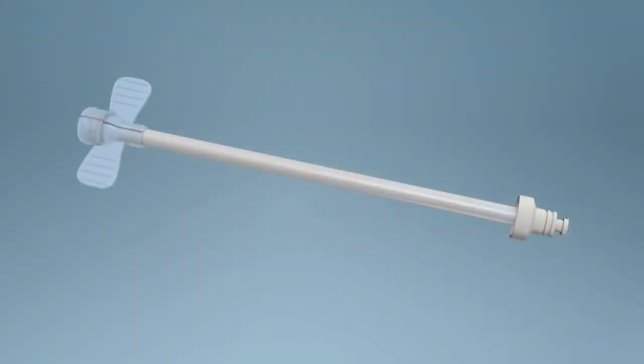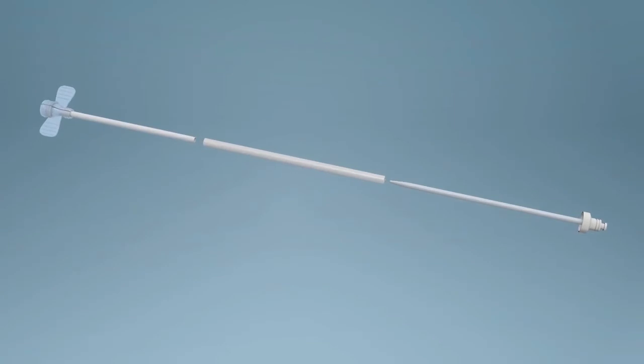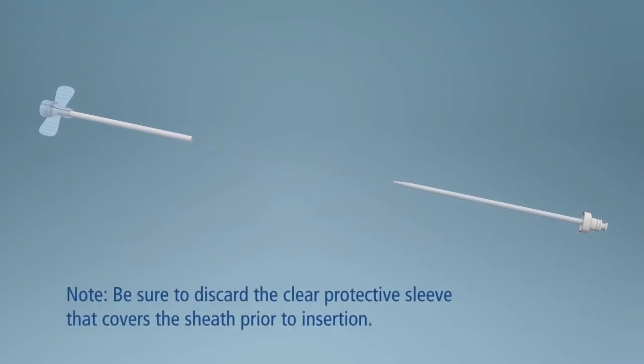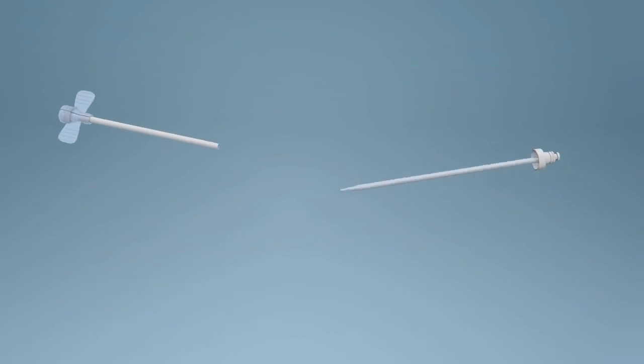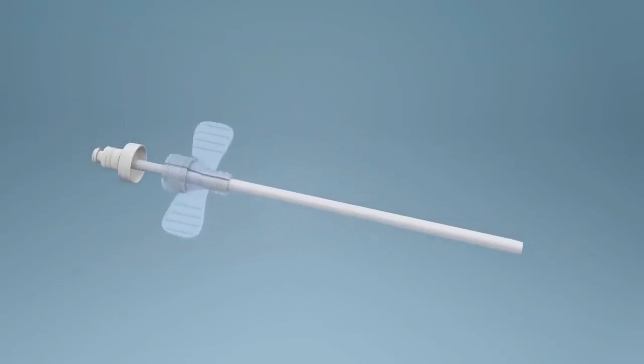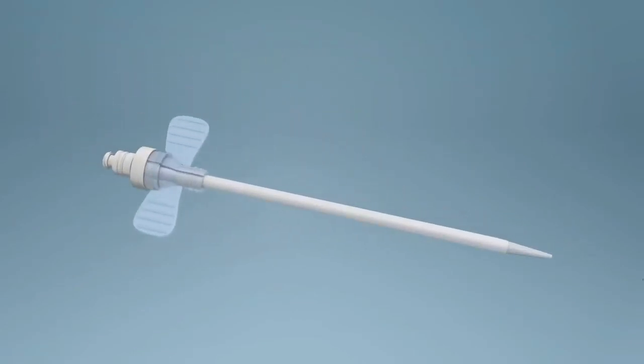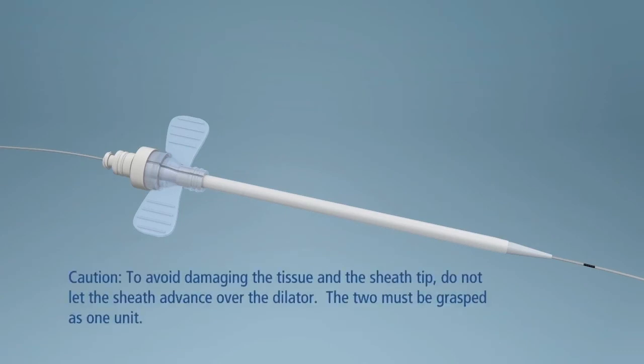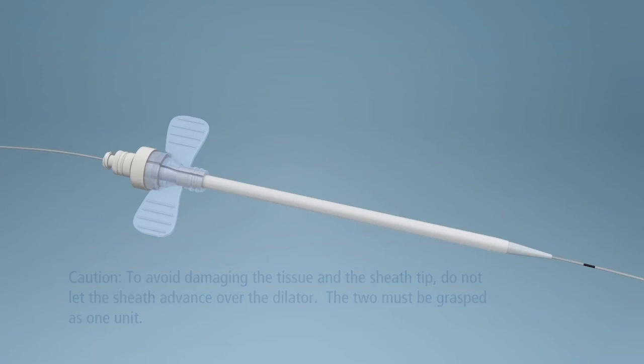Take the valved pull-apart safety sheath assembly from the package and remove the dilator from the end of the sheath. Note, be sure to discard the clear protective sleeve that covers the sheath prior to insertion. Insert the vessel dilator onto the sheath until the dilator cap folds over the valve housing and secures the dilator onto the sheath assembly. Thread the dilator sheath assembly over the guidewire. Caution: to avoid damaging the tissue and the sheath tip, do not let the sheath advance over the dilator. The two must be grasped as one unit.